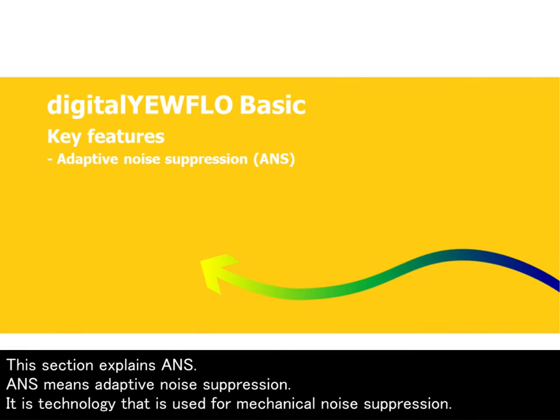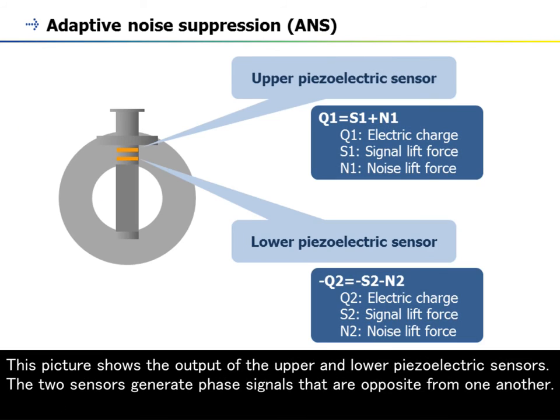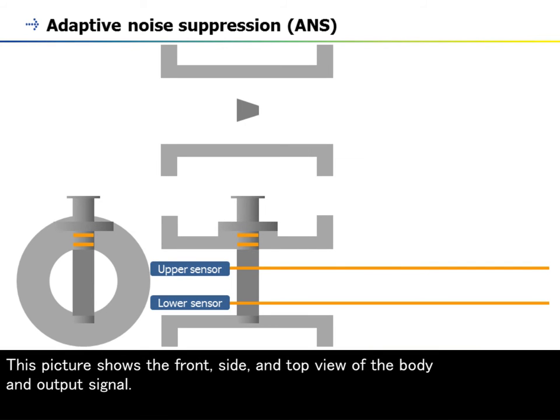This section explains ANS. ANS means adaptive noise suppression. It is a technology used for mechanical noise suppression. This picture shows the construction of the detector portion. The shutter bar assembly of the digitalYEWFLO uses two piezoelectric sensors. This picture shows the output of the upper and lower piezoelectric sensors. The two sensors generate phase signals that are opposite from one another, and the noise caused by vibration is superimposed on the signal at the same time. This picture shows the front, side, and top view of the body and output signal.